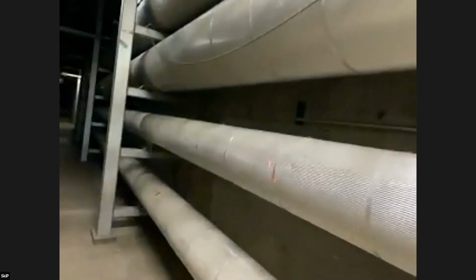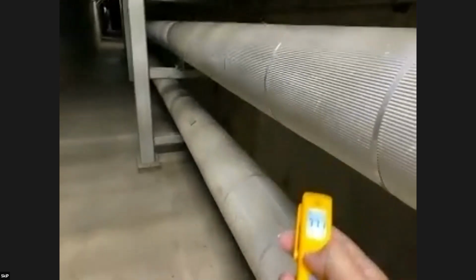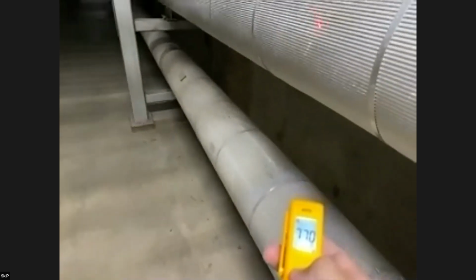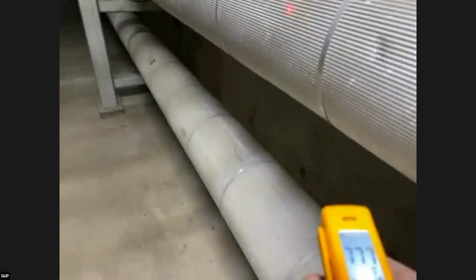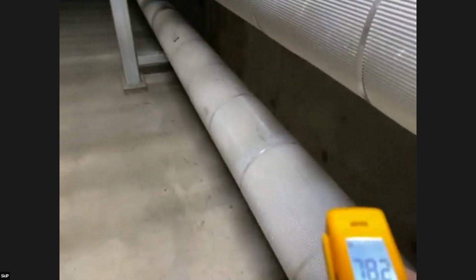So now we're walking in under the wall and going into LaCourte Hall. One thing I like to talk about at this section: the smaller lines are the hot water lines and the larger lines are the chill water lines. What Skip is doing is using a heat gun to show us the temperature of these pipes. In a perfect world, we'd insulate these so no energy could escape, and the outside of this jacket would be the same temperature as the area around it. But we can see a big difference in temperature, showing 78 up here, 81 or so on the bottom.